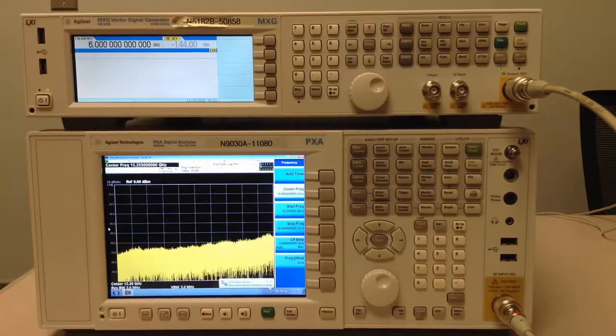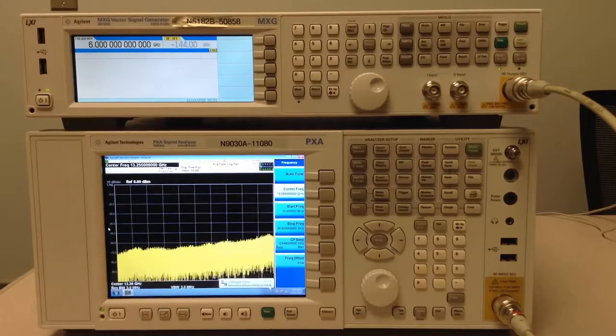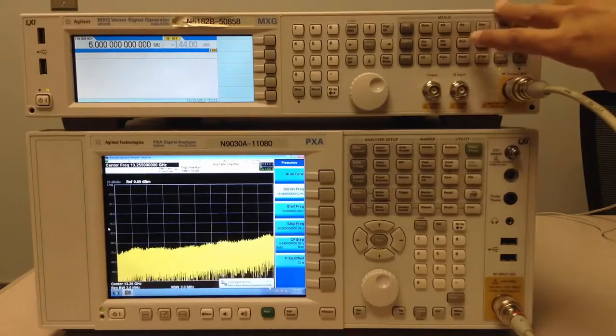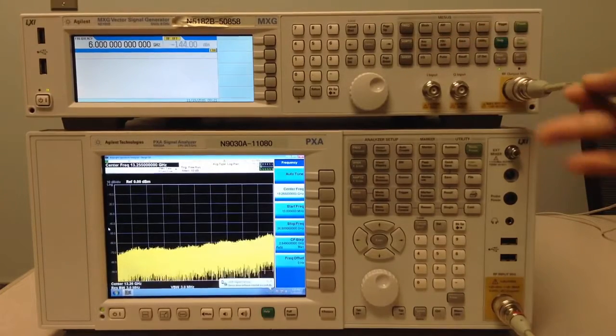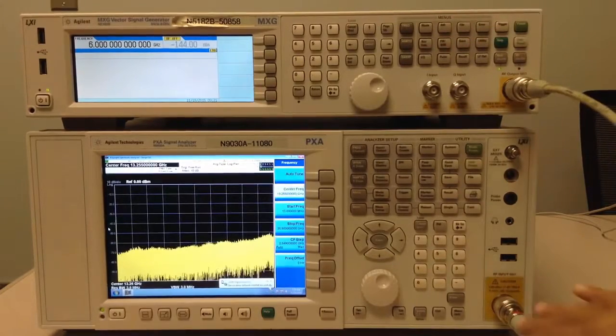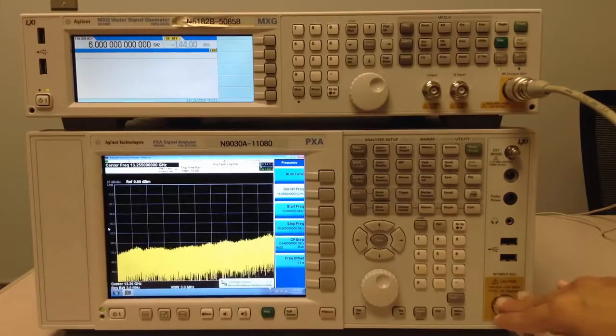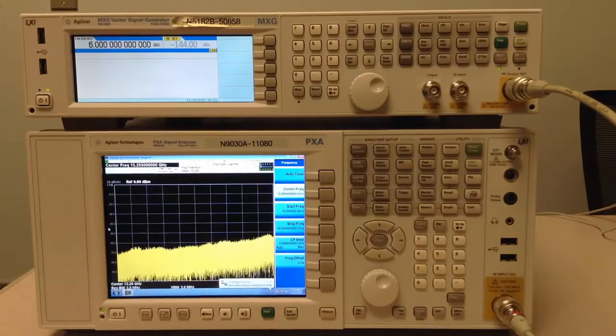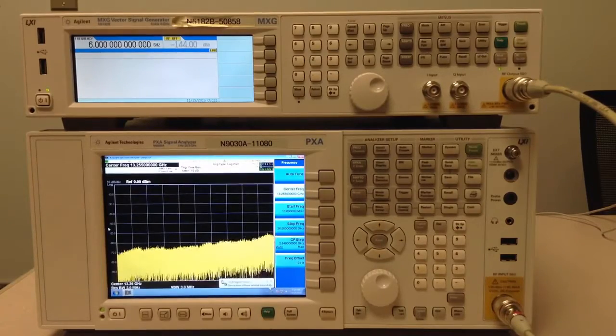Our setup is thus, the MXG creates the signal and provides RF output to the PXA's input which will in turn run the VSA software. Let's get started.